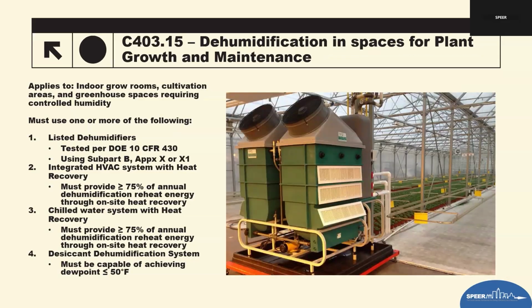And then C403.15, now we've got dehumidification in spaces for plant growth and maintenance. There was a section in the 21 that just continues to get expanded and clarified, in my opinion. But these spaces have very high latent loads due to plants, irrigation, soil moisture that must be maintained. Because dehumidification energy can be extremely high in these spaces, the code requires equipment that is either highly efficient or recovers heat that would otherwise be wasted.